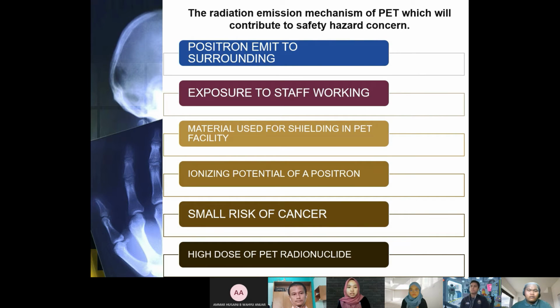There is an additional effective dose rate from natural background radiation. The dose rate in areas accessible to the public must not exceed 2 mrem in any given hour, 0.02 mSv per hour. Members of a public area include institutional staff members whose assigned duties do not involve exposure to radiation sources. So that's all from my explanation.